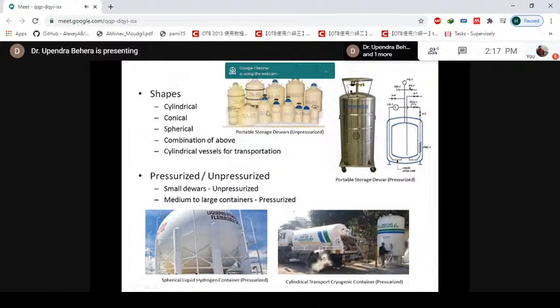These small dewars are not pressurized containers, meaning when you want to remove the liquid or cryogen, you just lift off and pour into your system, or take it to the subsystem and pour. These have to be handled carefully because, as already explained, the inside containers are suspended from the outer shell with fiberglass, and the connection is done with special epoxy adhesives. So we have to handle it carefully, otherwise there is a chance it may break. All filled containers must be handled carefully.